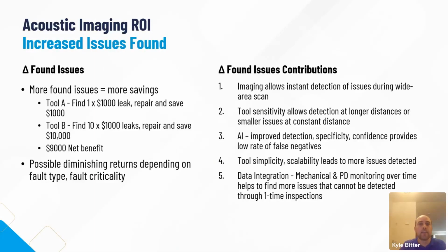Then there's data integration, whether it's mechanical and PD monitoring over time. We have a data management software, our DMS software, that we pair with our ultra probes and grease caddies to trend the data of mechanical assets over time. You also have the ability inside the software to keep a history of all the reports you run with the camera. So if I'm only using it for leak detection, or only for partial discharge, you can store those reports and see how often things are failing, how often leaks are actually being presented on certain assets throughout your facility.